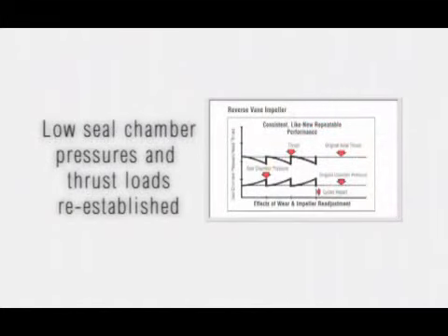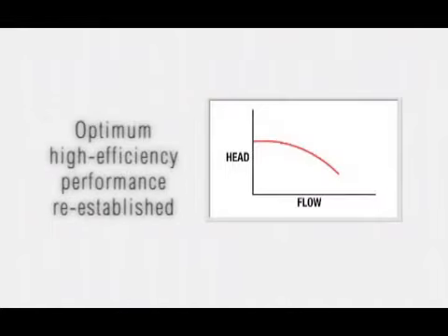The lowest possible seal chamber pressures and thrust loads are re-established after every impeller adjustment throughout the life of the pump. Also, the pump's original hydraulic performance is re-established after every impeller reset for optimum performance and lowest possible energy consumption.